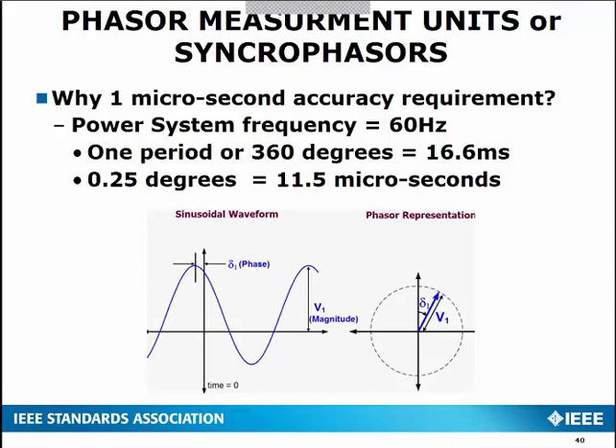And why is the 1 microsecond accuracy important? Well, the North American power system runs at a frequency of 60 hertz, which is pretty slow for most electrical applications, but in our case, one period, or 360 degrees, is 16 milliseconds, and an accuracy of a quarter of a degree would be 11.5 microseconds.